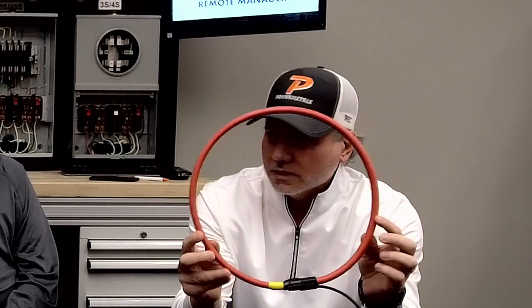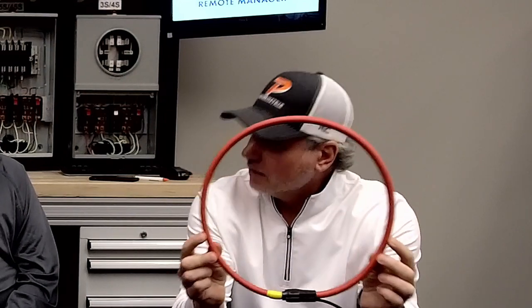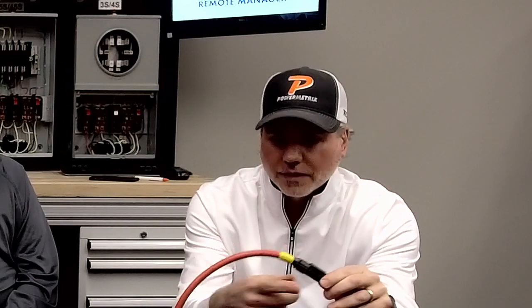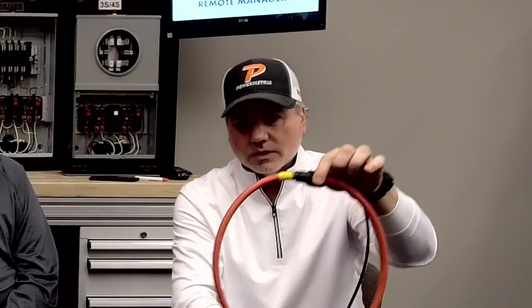So this is really an art form on how you connect these out in the field. Some other things to know, that connection point, even though it's not metal on metal, if you have that sitting on a conductor, you're going to get worse readings. So a lot of people will start double wrapping. They want to make this window smaller because anything that finds its way into this window, whatever kind of magnetic field, is going to get measured. So as we double wrap that, we now make that window smaller so there's less chance of that happening.